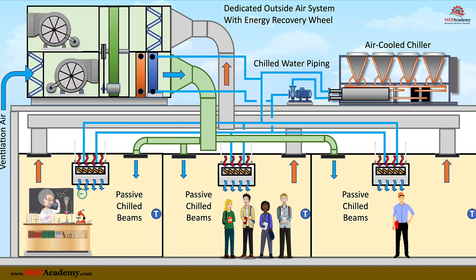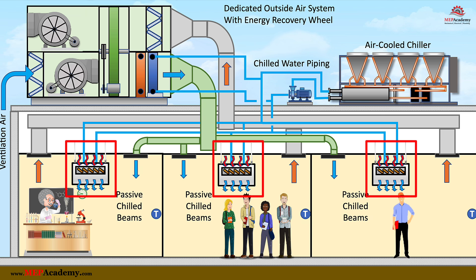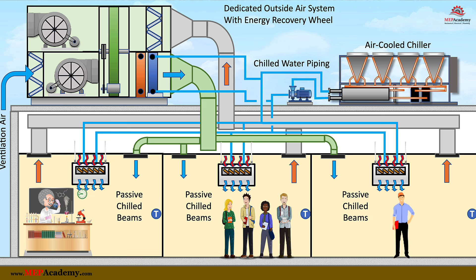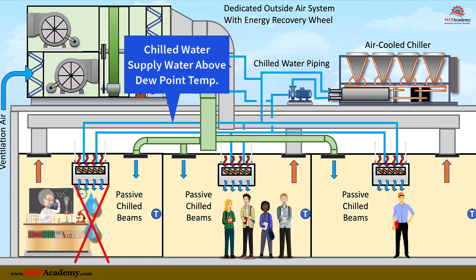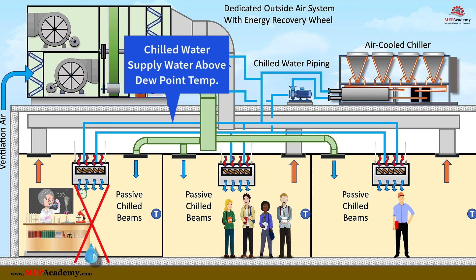In chilled beam applications, it's crucial to prevent reaching the dew point temperature and creating condensation. Chilled beams don't have condensate drains, so it's important moisture doesn't occur on the face of the chilled beam. By controlling humidity and maintaining the surface temperature of the chilled beam above the room's dew point, we avoid condensation, ensuring efficient cooling without the risk of moisture forming and dripping into the space below.